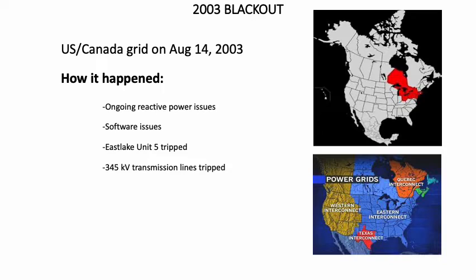There were three 345 kilovolt transmission lines that tripped due to contact with a tree. This worsened the event and caused cascading transmission lines to trip due to being overloaded now that they had to take on the extra load from the loss of these three lines. And so they ended up tripping due to being overloaded at under voltage. From all this, frequency oscillations began, and it split the remaining grid into small islands, which led to an even greater blackout.